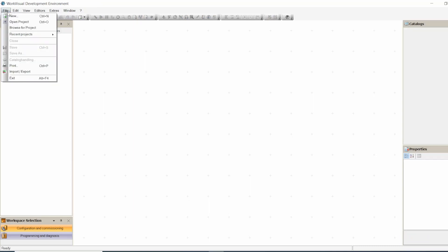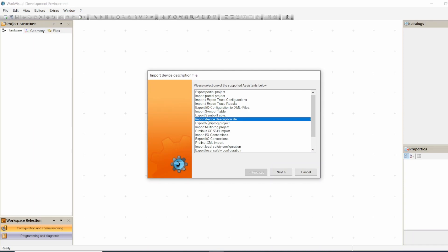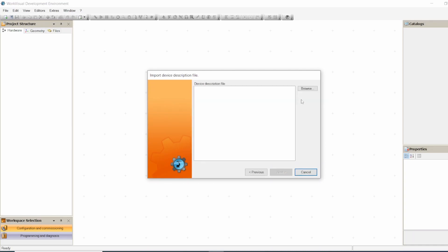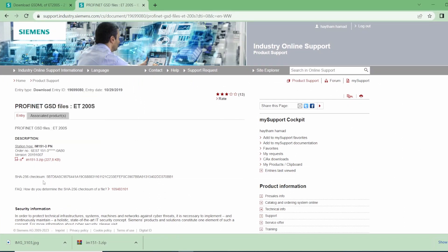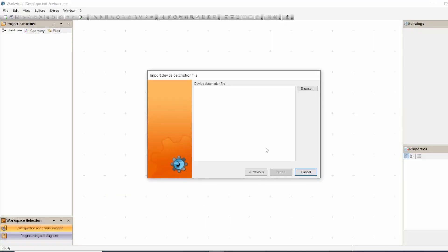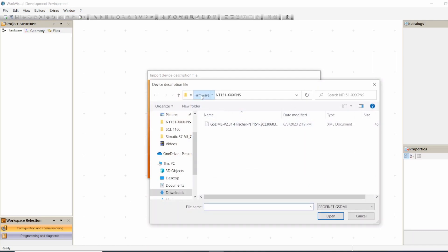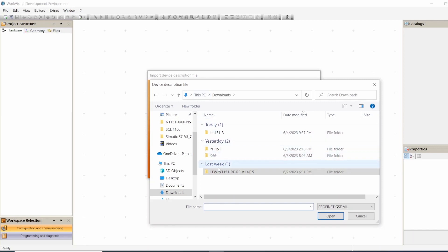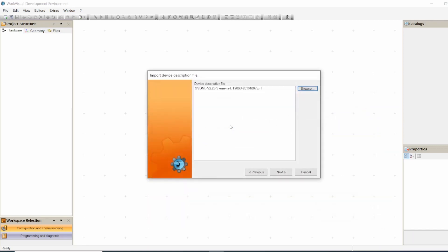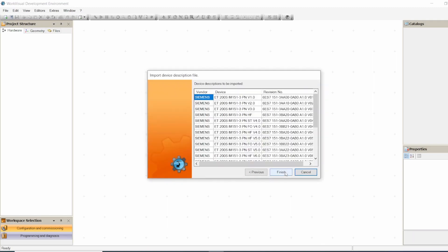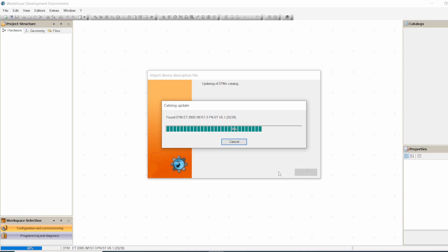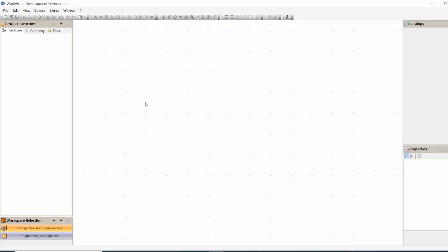Now we have no project open. We go to File > Import/Export > Import Device Description File > Next. You will already have downloaded the GSD file from the internet — I went to the Siemens website, and this is the link for the GSD file for the ET 200S that I'm using. I will add this link under the video. Then we browse to where we saved the GSD file, select it, click Next, and it downloads all the GSD files for the inputs, outputs, and everything. Finish — okay, it's done.